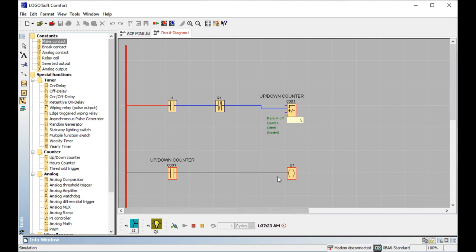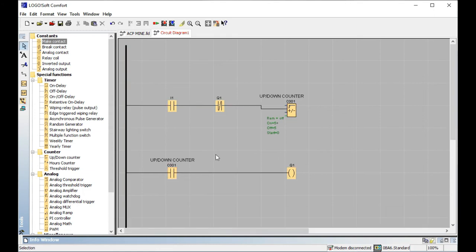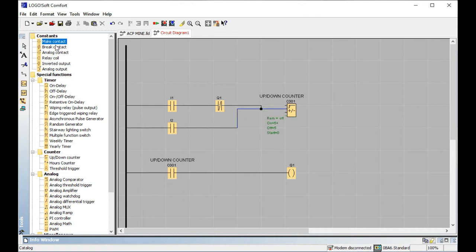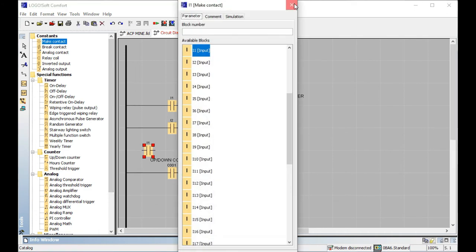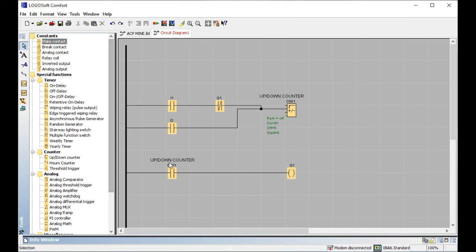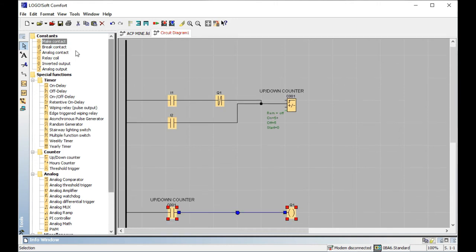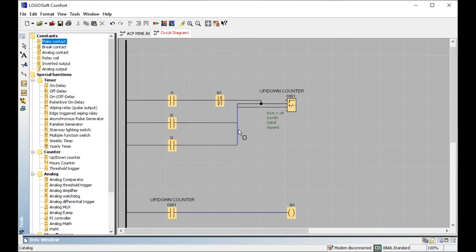When I start the simulation — one, two, three, four, five — after five, it is not capable of accepting another sensing pulse because the break contact is in place. That's the up counting. Now for the down counting, I use a second sensor input (I2). I add the down count sensor connected to the direction input.